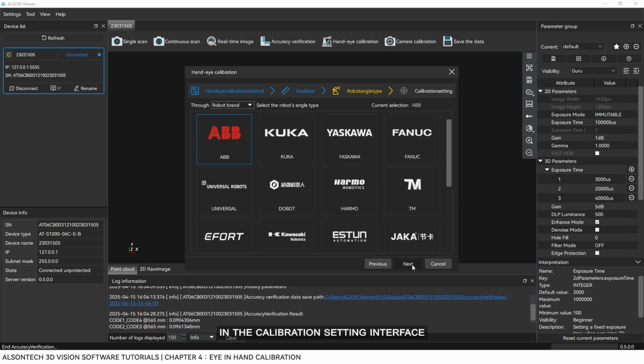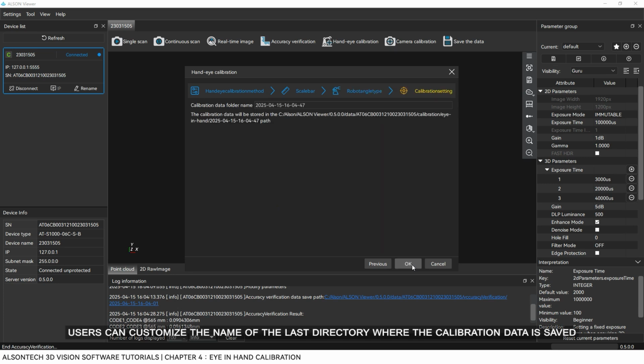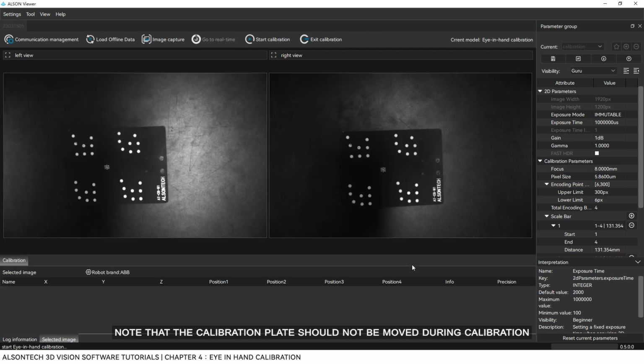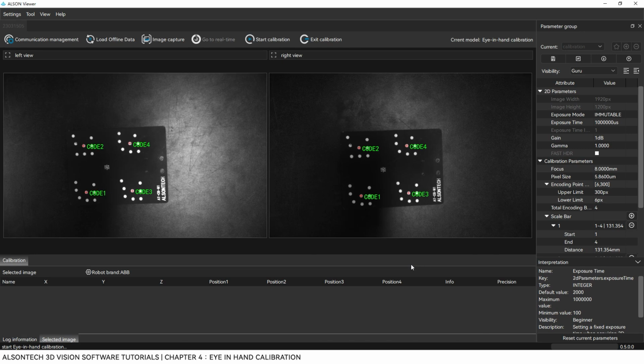Click Next. In the calibration setting interface, users can customize the name of the last directory where the calibration data is saved. Okay, note that the calibration plate should not be moved during calibration and should be placed horizontally as far as possible. Place the calibration plate in the center of the field of view and check the distance by adjusting the exposure and other parameters in the right-hand parameter group. The real-time image displayed in the middle window of the interface can be adjusted to achieve a better effect.